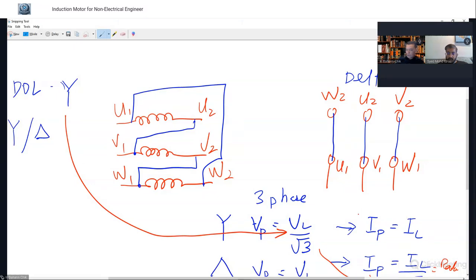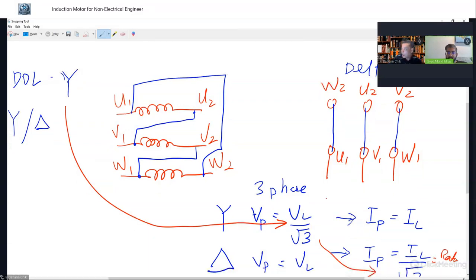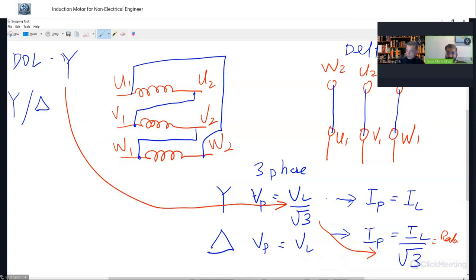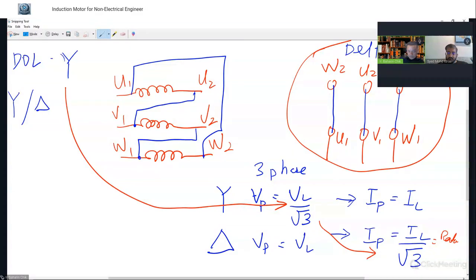Apa soalan tadi? Sorry? Ada yang tanya macam mana kita nak choose star atau delta ataupun star delta ni just a starter je lah yang maksudnya. Yes, normally the motor vendor will give you the choice, the ability to use delta or star. But now you have to see what is the advantage of connecting in star, and what is the advantage of connecting in delta. Like I said just now, if putting in star, the phase voltage is actually V line divided by square root 3. So that is the voltage. You have a reduced voltage during starting, right?